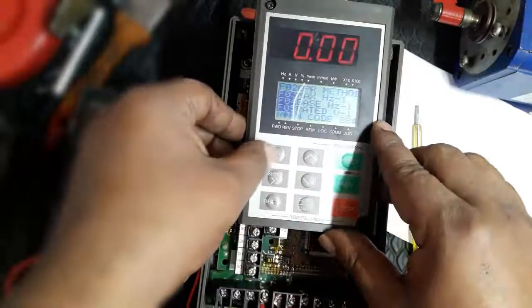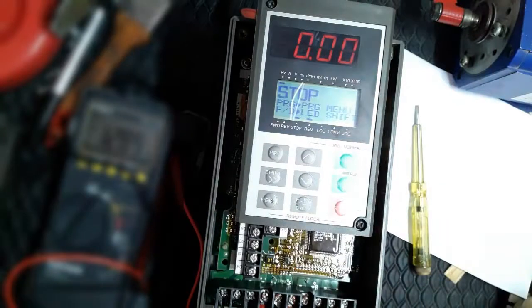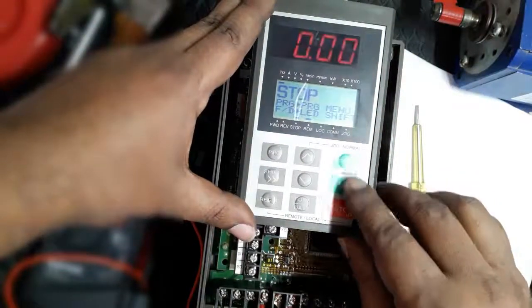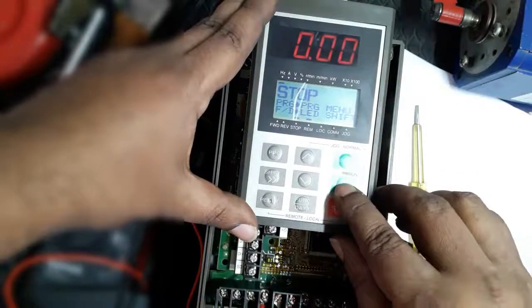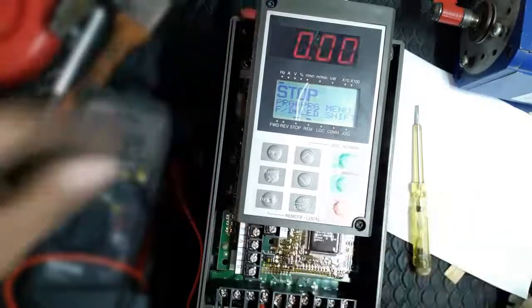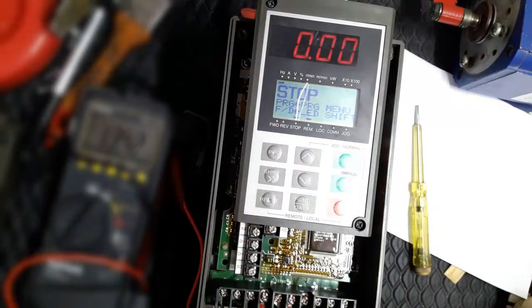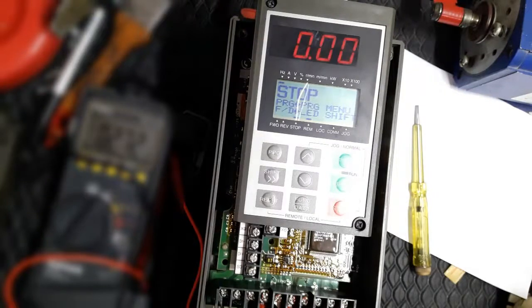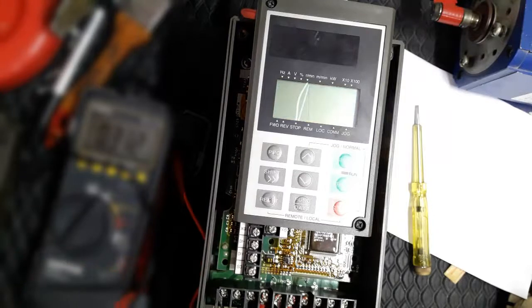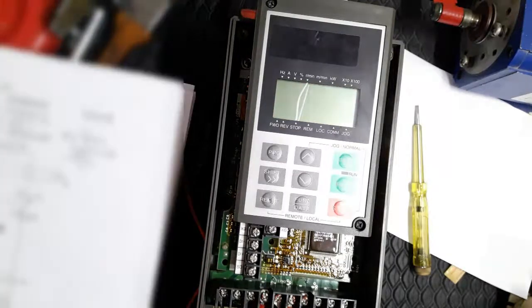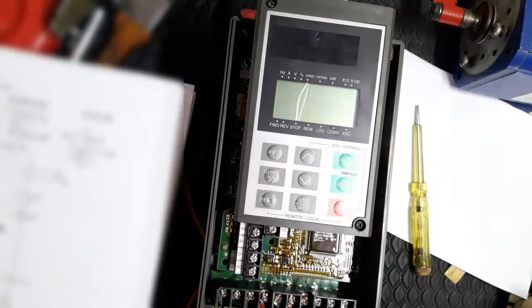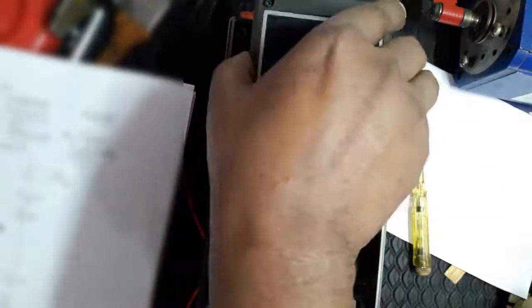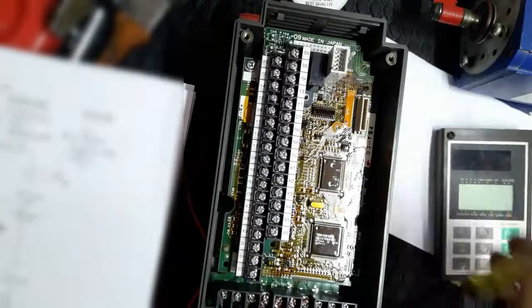Completed setting program for external operation. Here we're setting run command and frequency command, so we can run and vary frequency by potentiometer. Run command is controlled by switch. Now we shut down the inverter to connect the potentiometer and run command connection.